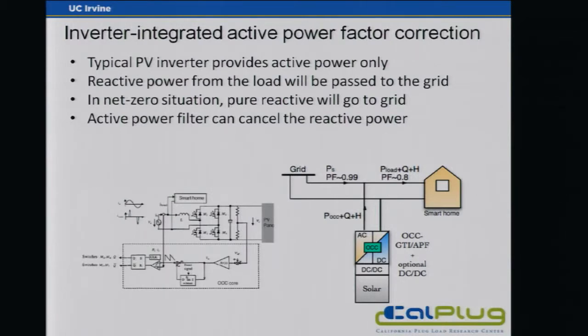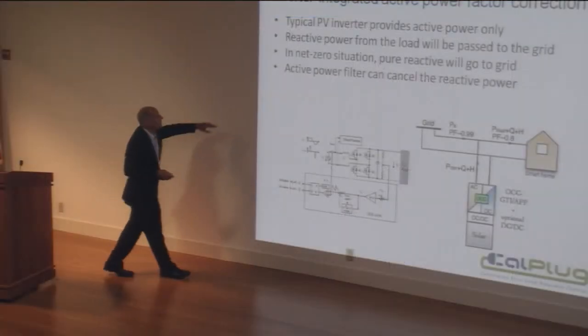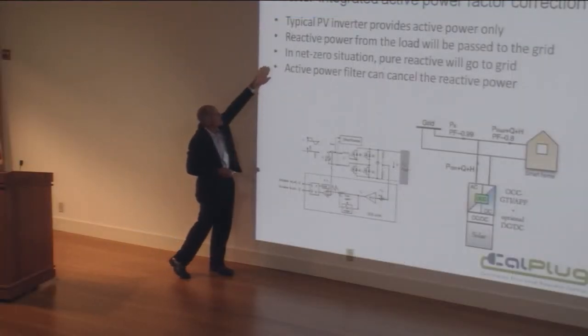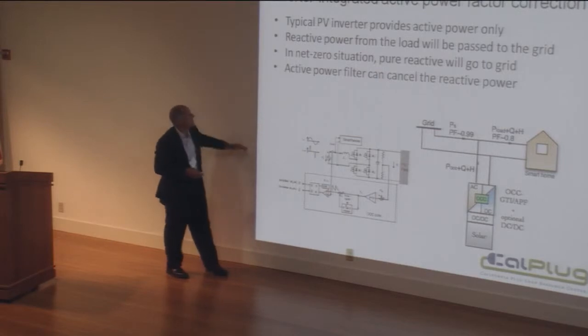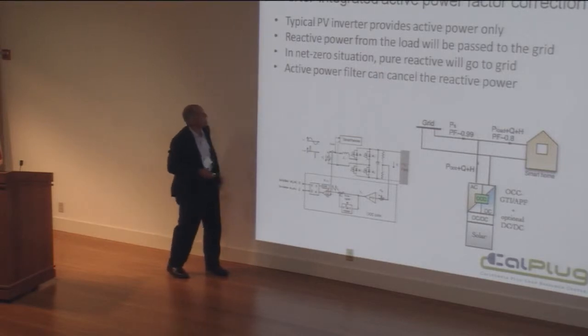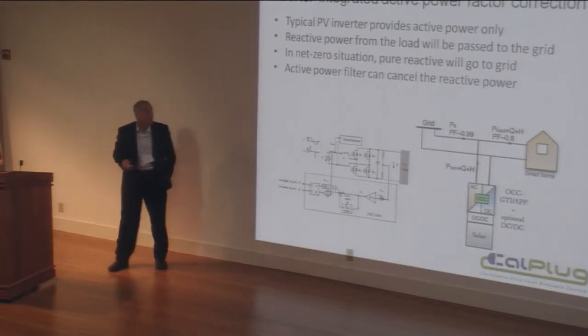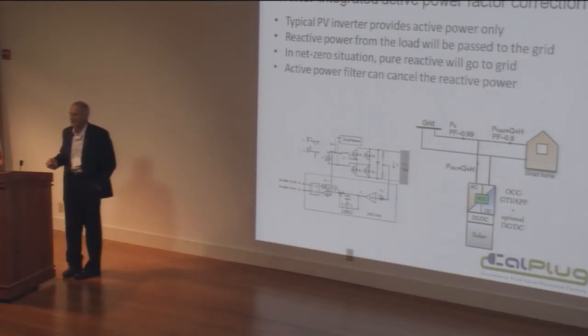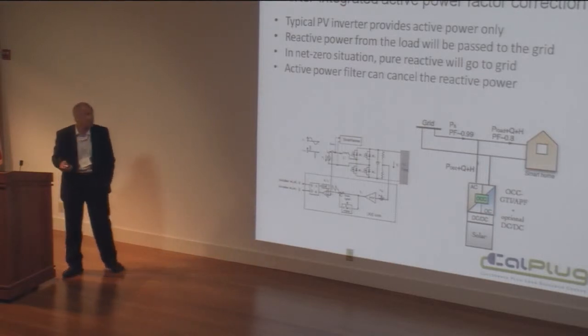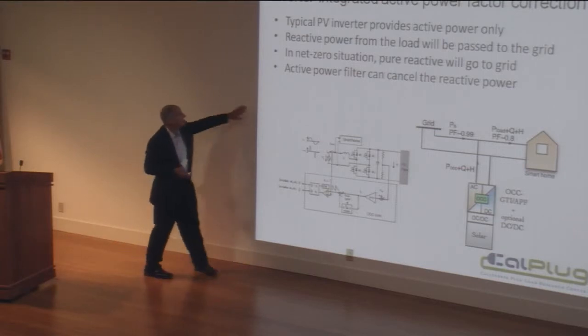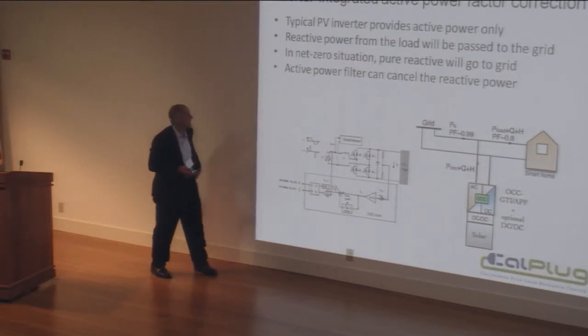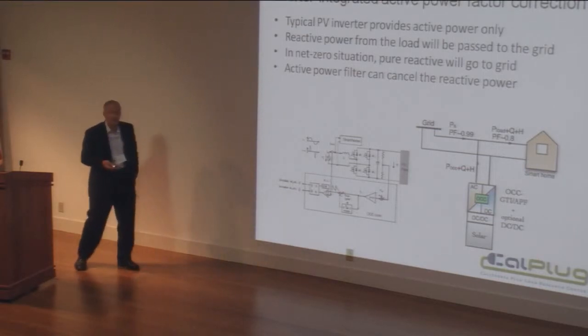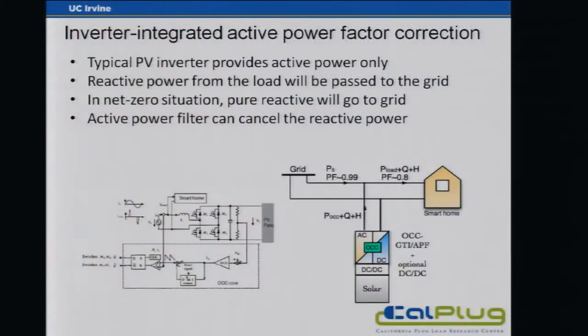A typical PV inverter provides active power only, and the reactive power from any of the loads is passed to the grid. So in a net zero energy situation, you're effectively giving mostly reactive power to utilities, and they cannot charge you for that. The idea here is to put in an active power filter that can cancel that reactive power.